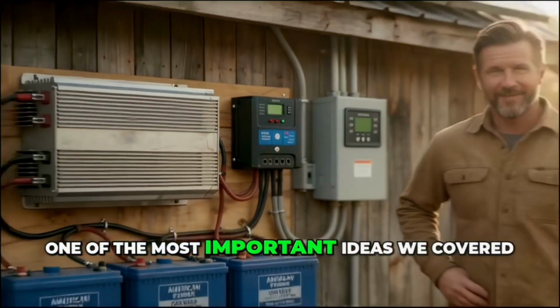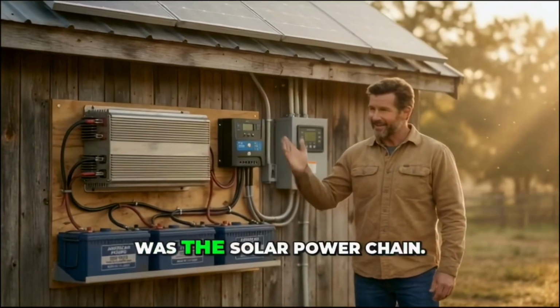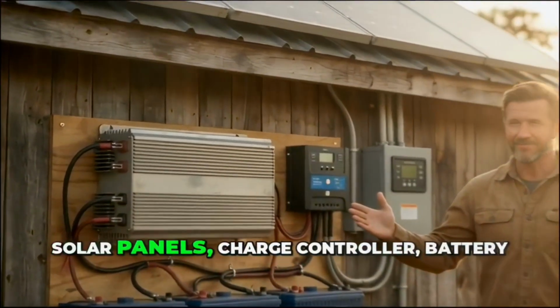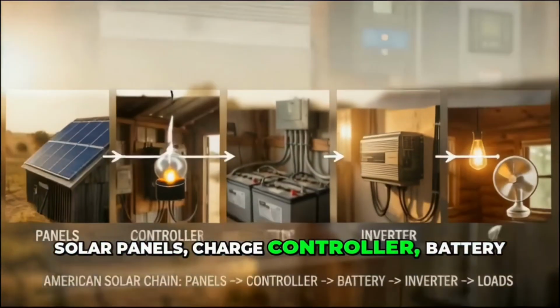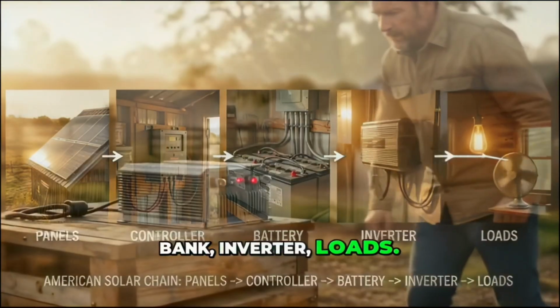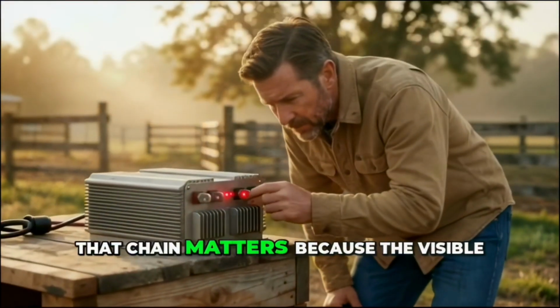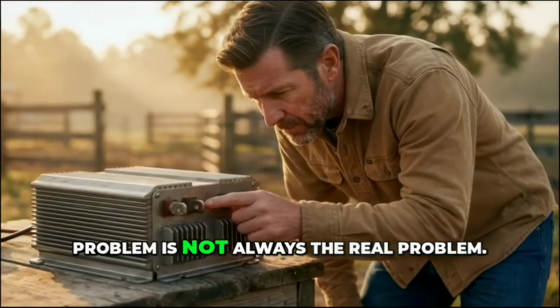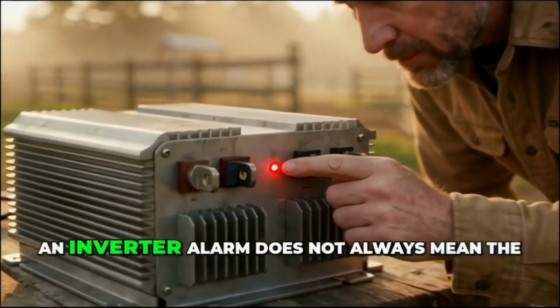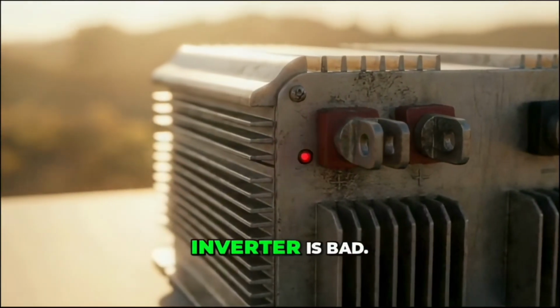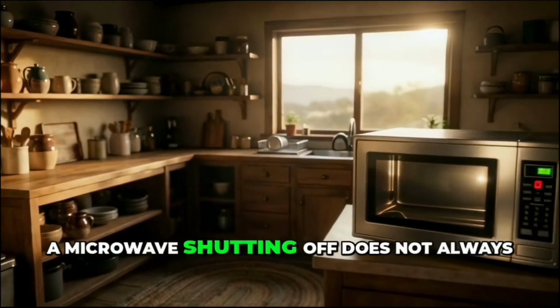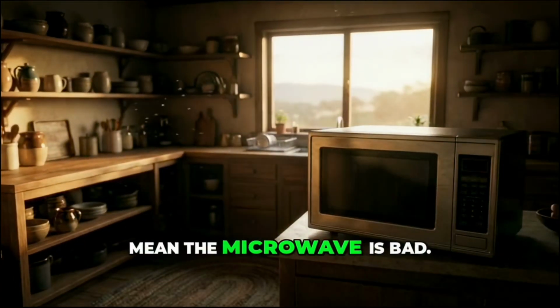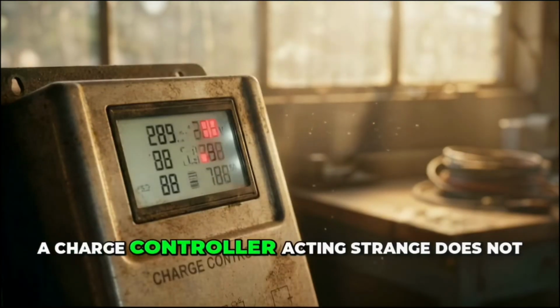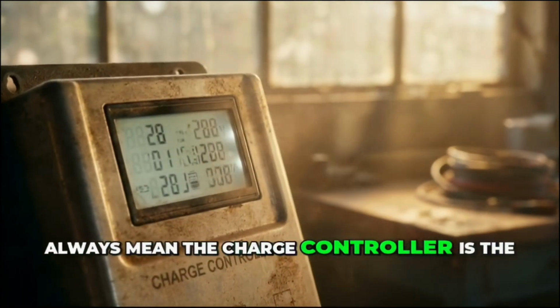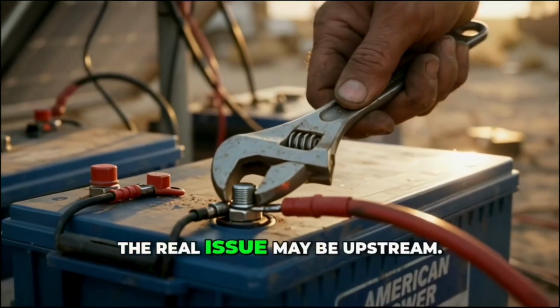One of the most important ideas we covered was the solar power chain: solar panels, charge controller, battery bank, inverter, loads. That chain matters because the visible problem is not always the real problem. An inverter alarm does not always mean the inverter is bad. A microwave shutting off does not always mean the microwave is bad. A charge controller acting strange does not always mean the charge controller is the problem. The real issue may be upstream.